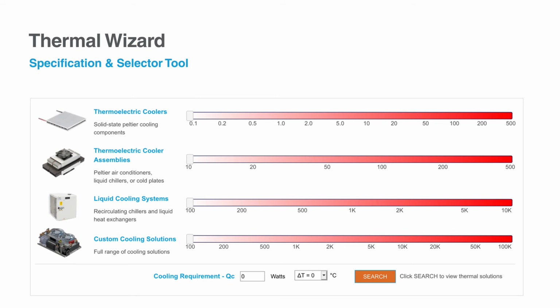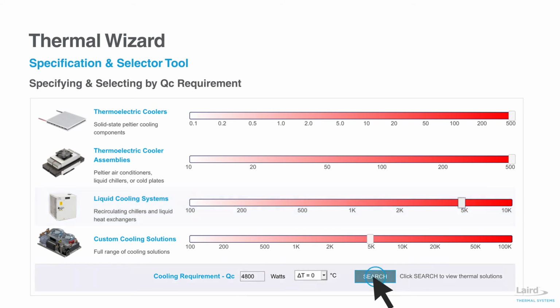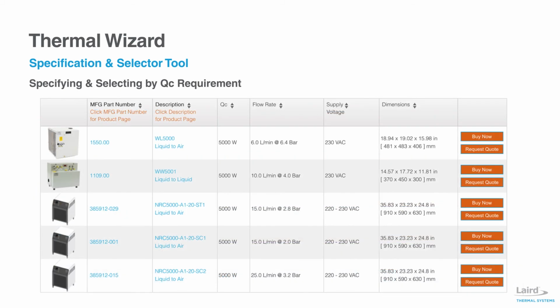Laird Thermal Systems has developed the Thermal Wizard to help engineers simplify and speed up the process of specifying and selecting the right thermal solution. The web-based specification and selection tool assists engineers in quickly determining the optimum cooling solution based on their cooling requirement. In this example, moving the QC slider to the application's heat load of 4,800 watts and clicking Search produces a quick selection table of the optimum recirculating chillers for your application. The flow rate requirement will help you determine which model to choose for the optimum selection. Click on the part number to view the interactive data sheet and complete your selection.